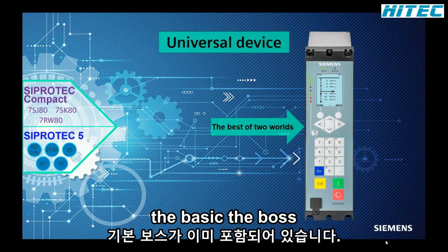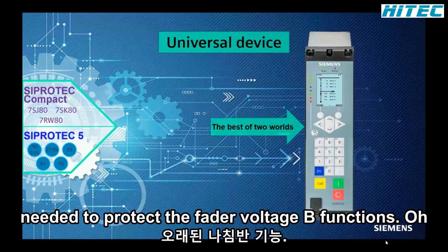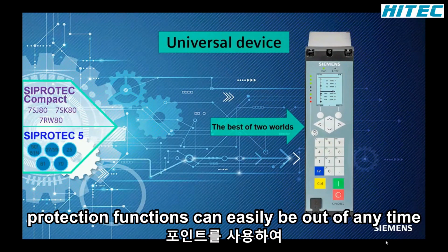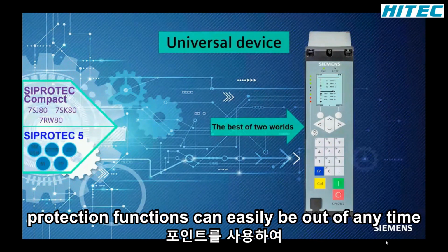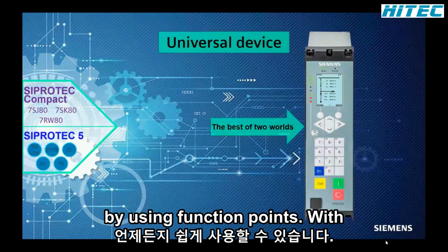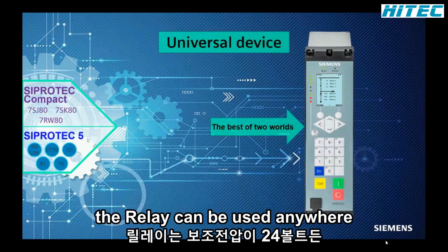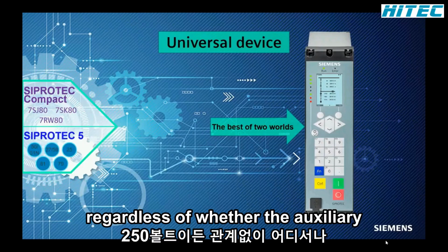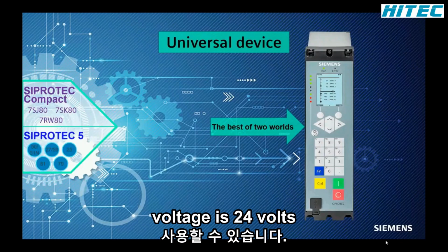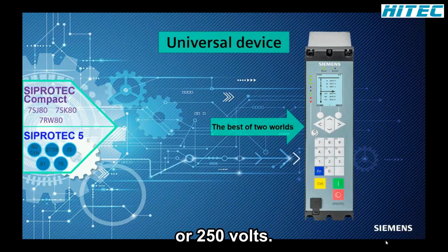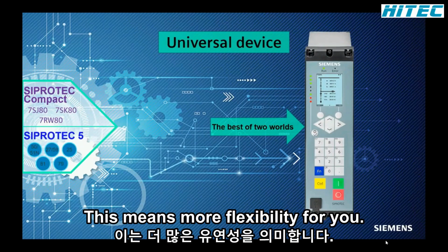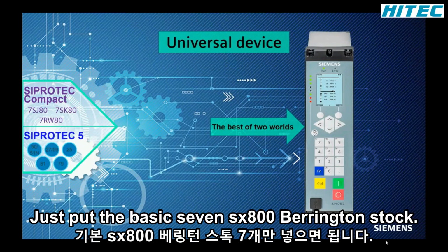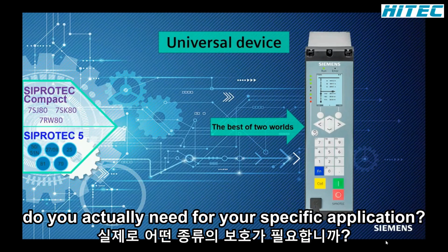The basic device contains already all the current-based functions needed to protect a feeder. Voltage-based functions or motor protection functions can easily be added anytime by using function points. With our universal power supply, the relay can be used anywhere, regardless of whether the auxiliary voltage is 24 volts or 250 volts. This means more flexibility for you. Just put the basic 7SX800 variant in stock and then define later what kind of protection you actually need for your specific application.